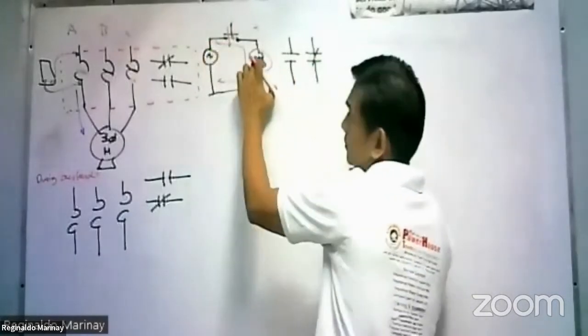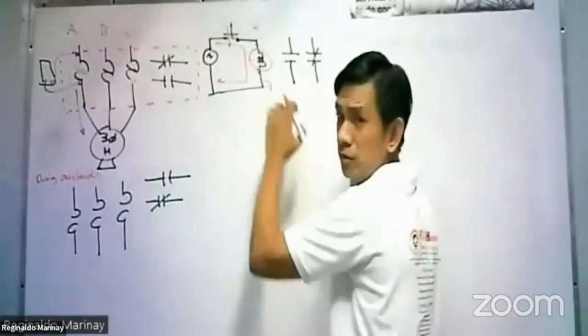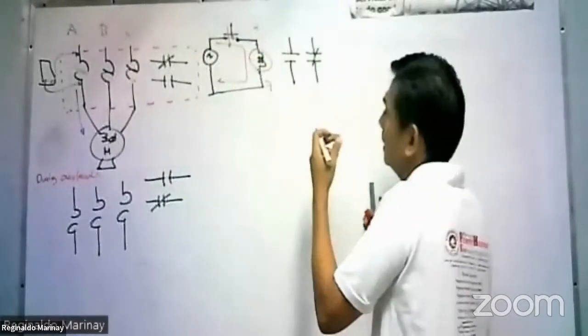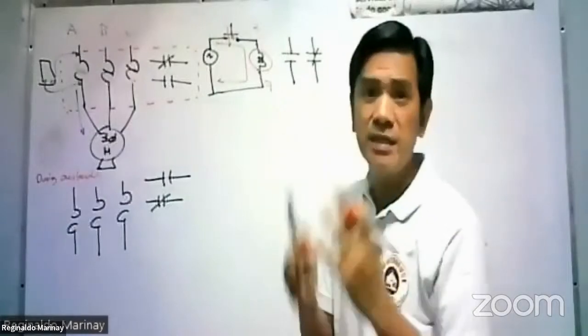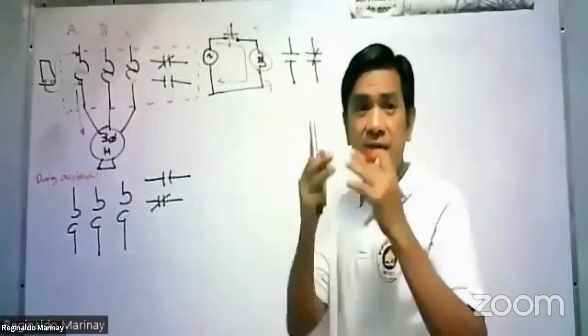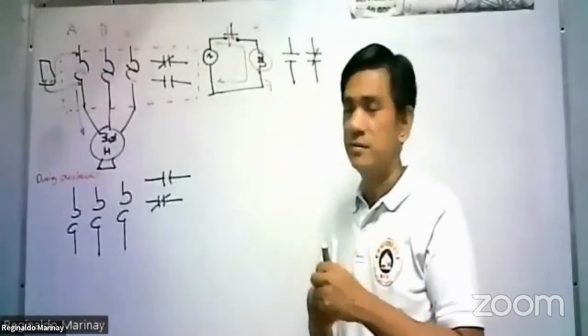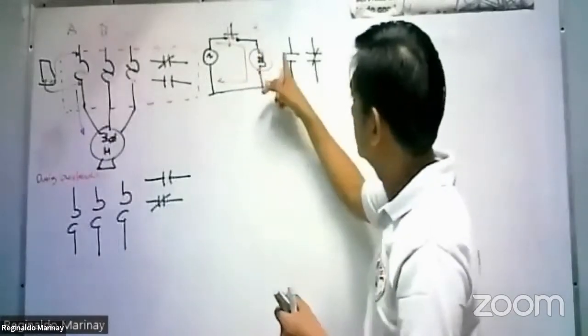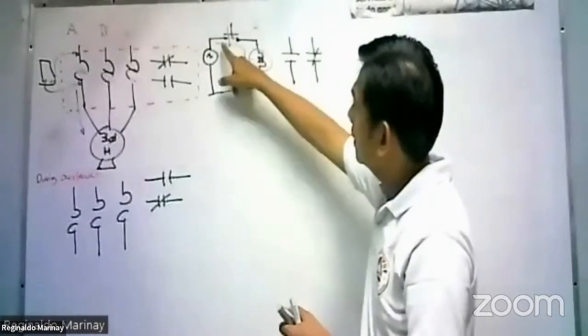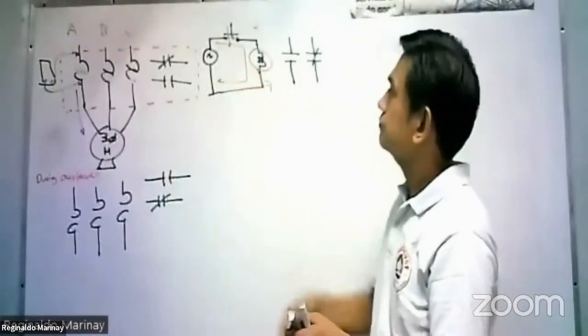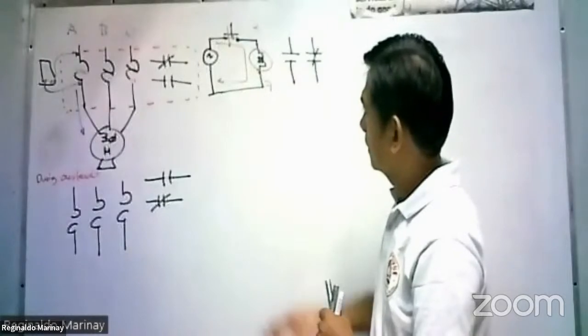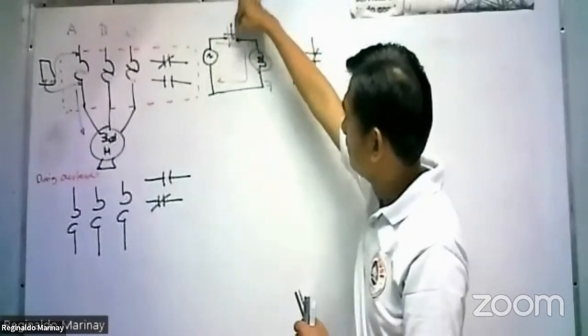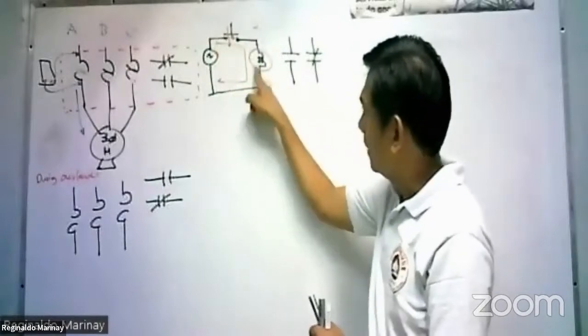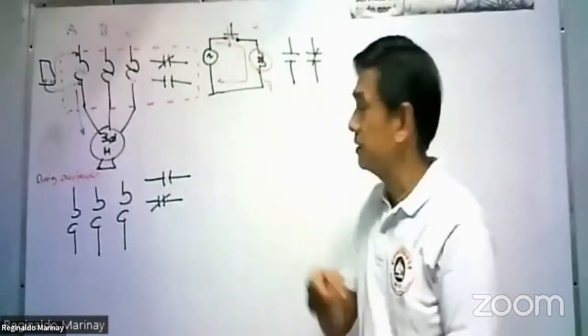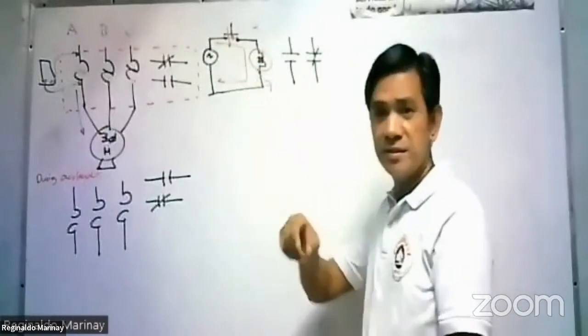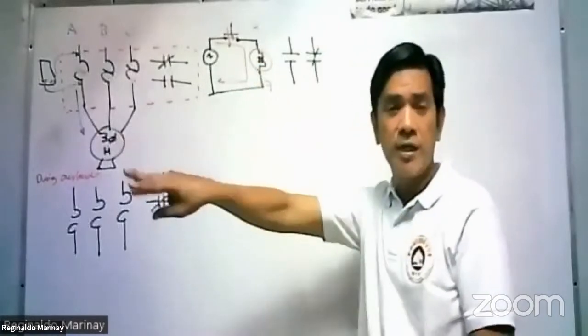Once you energize this coil, this holding coil, that coil of the timing relay, it depends on your setting. Let's say you have a 3 second setting on your timing relay. Once you energize it, the current will flow here. Once this becomes energized, that will start counting. 1, 2, 3.